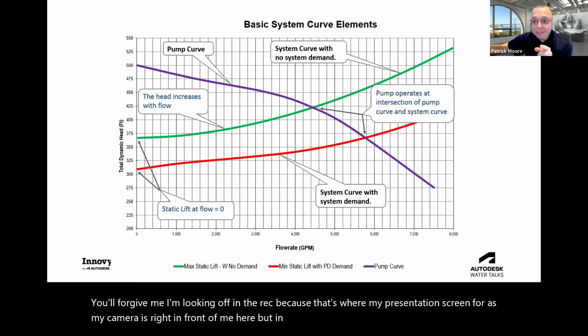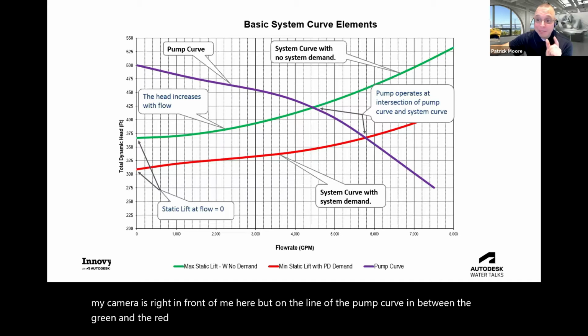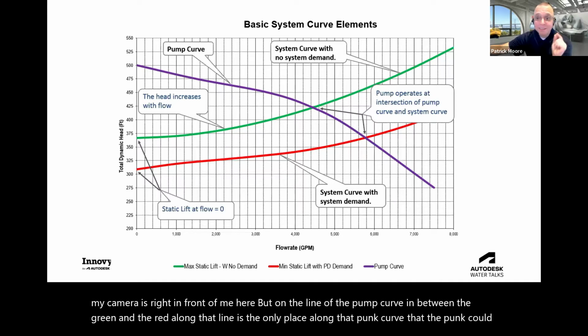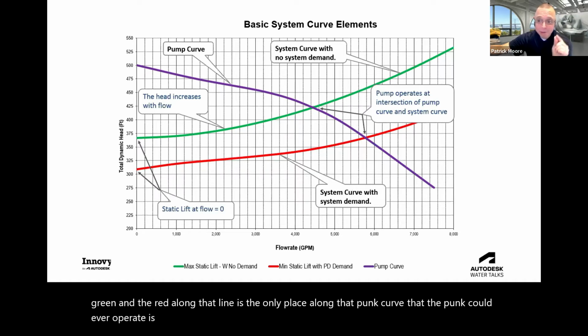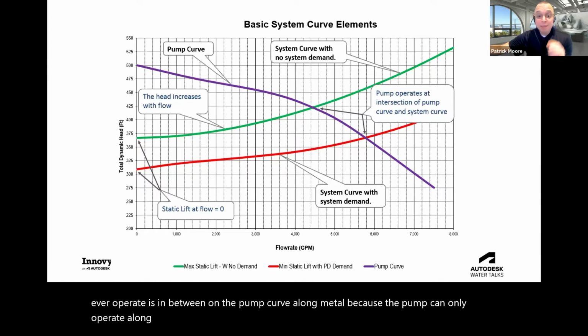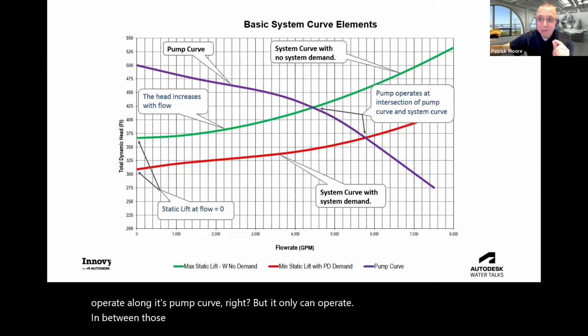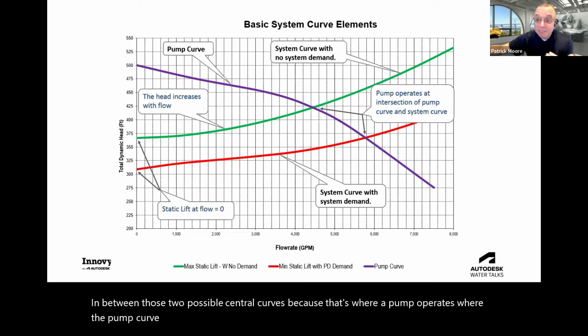But on the line of the pump curve in between the green and the red, along that line is the only place along that pump curve that the pump could ever operate, because the pump can only operate along its pump curve, right? But it only can operate in between those two possible system curves, because that's where a pump operates, where the pump curve and the system curve intersect.